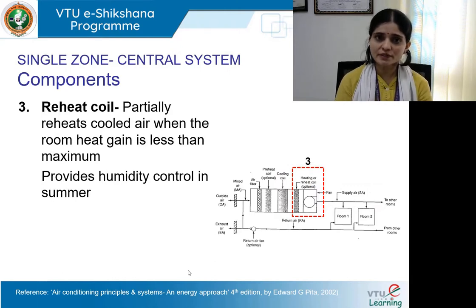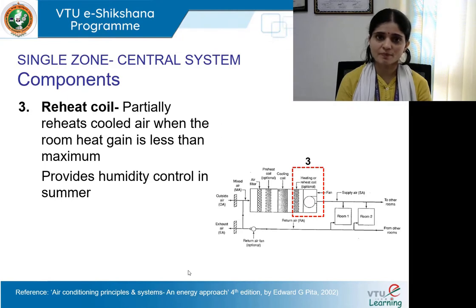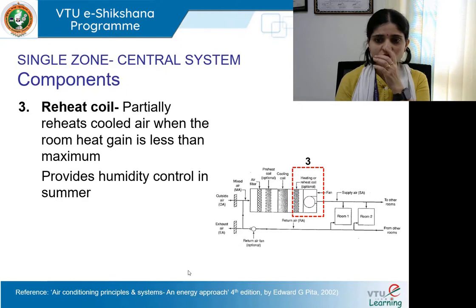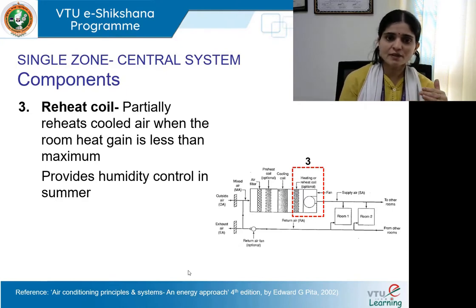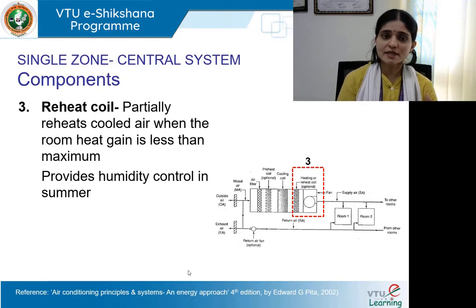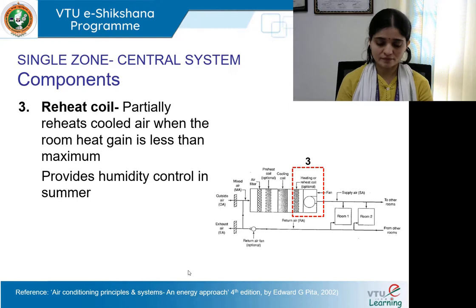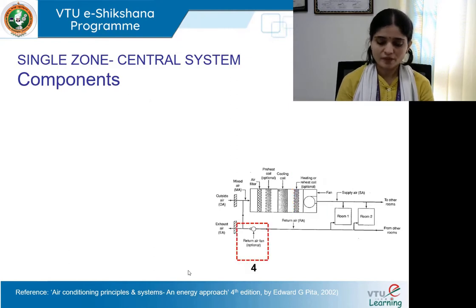Number three: the reheat coil. It partially reheats the cooled air when the room heat gain is less than the maximum. It provides humidity control during summer. This heating or reheat coil can be activated when the thermostat senses that the room heat gain is less than expected or the maximum.